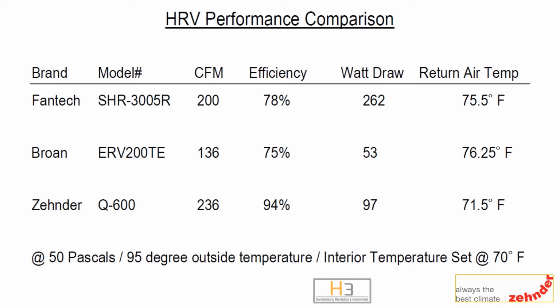There is a vast difference when you compare the performance of various HRVs on the market today. Even though Zehnder units have much more advanced features, the main consideration with a heat recovery ventilator is the heat recovery and the amount of ventilation. When delta T exceeds 20 degrees Fahrenheit, performance becomes quite clear. This is when an HRV should shine, not falter. The amount of CFM provided at a specified efficiency level is critical to optimizing indoor air quality. Better motors equate to lower watt draw, saving more energy, especially since these devices run continuously. ECM motors with lower watt draw are quieter as well.